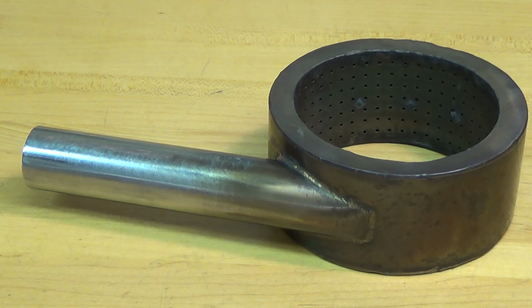Although I must admit I made a mistake in the construction of this burner. There is an anti-flashback screen used behind the flame sheet. The flame sheet is the piece that you see that has all the perforated holes. The anti-flashback screen is utilized to prevent flashback into the burner annulus. The screen has provided an effective reduction in the jet or hole size in the flame sheet, and thus limiting the burner output to approximately 2,000 watts.